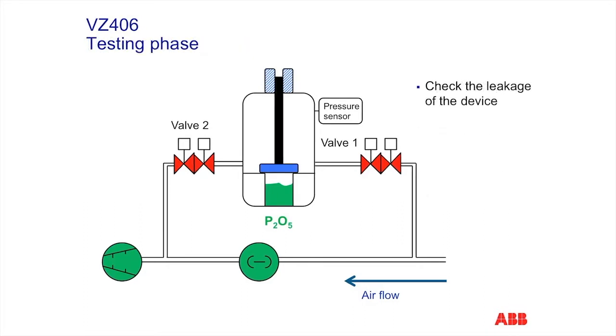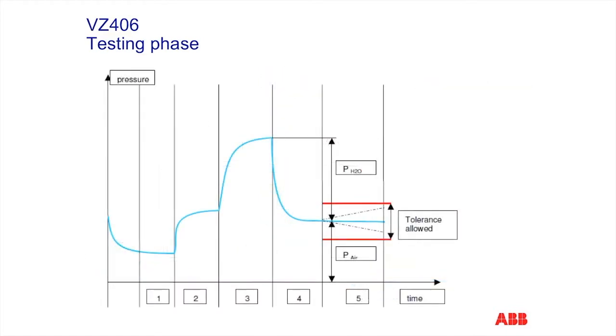The phosphorus pentoxide chamber closes, and the 2 valves remain closed, and the system is tested to ensure that there are no leaks. This shows the sequence of steps involved in taking a measurement. The integration of these points over time results in the amount of water extracted from the process.